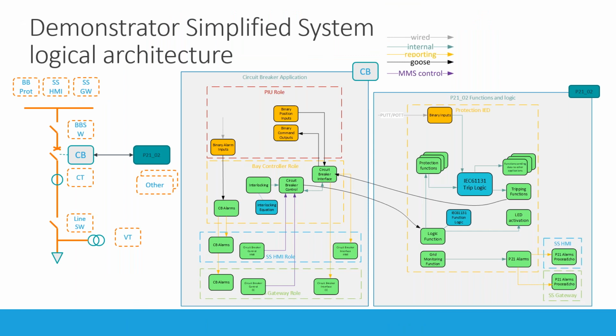When we have the circuit breaker application template and the distance protection application template, and bring both together in a system, these applications can interact with each other. The trip goes from the right to the left, from the tripping function of the distance protection to the circuit breaker interface, which uses the trip and forwards it to the binary outputs. We also have the circuit breaker control function providing a signal to the logic inside the distance protection function - I think that's the signal that activates the switch onto fault zones, for example.